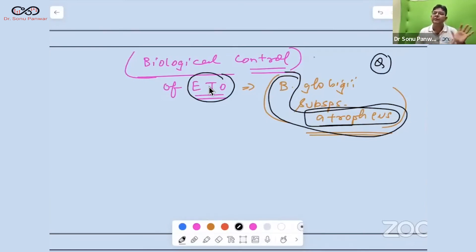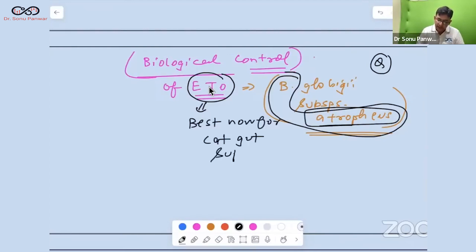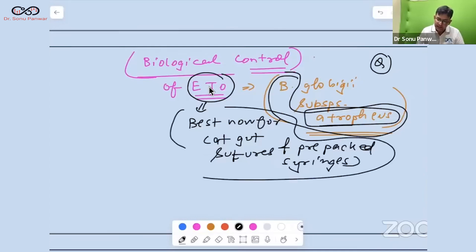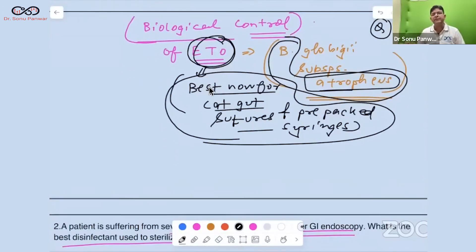Ethylene oxide is the best high-level disinfectant used in hospitals for ICU machines such as respirators and heart-lung machines. It is also the best sterilization method for catgut sutures and pre-packed syringes — better than gamma radiation. It is also used for dental equipment and similar hardware.